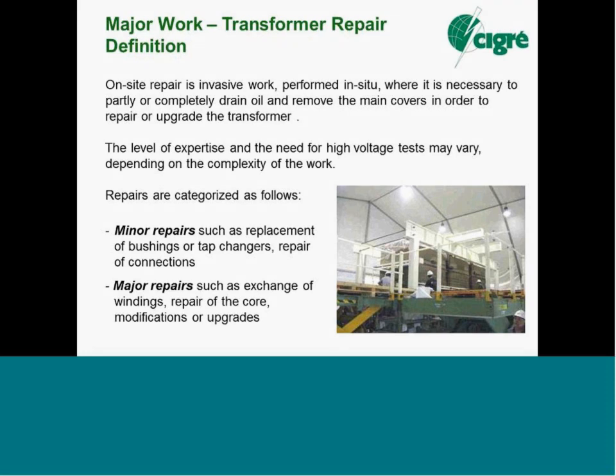If we decide on a new technology transformer, with lower losses in the iron loss and the copper loss, would that be a consideration in the overall costs of the exercise? You'll see some nice examples. It's very interesting to see what was in the mix, in the balance of costs, to decide on on-site repair versus off-site repair versus replacement. A very interesting area of the guide to read.